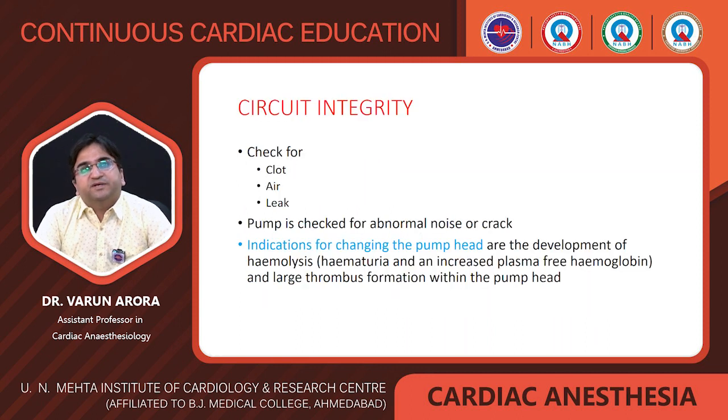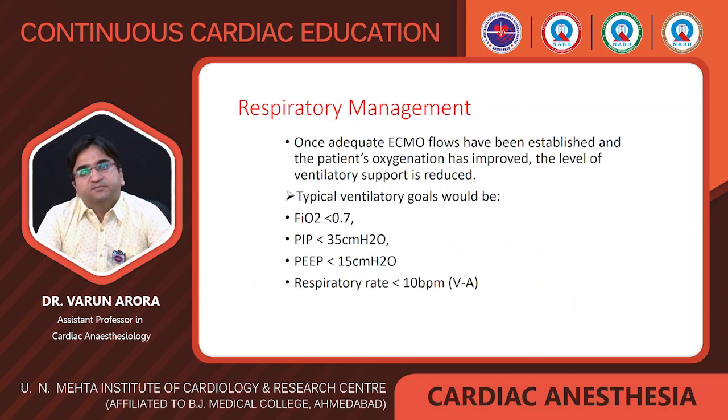Now coming to the circuit integrity. Check for clot, air and leak. Pump is checked for abnormal noise or crack. Indications for changing the pump head are development of hemolysis, hematuria and increased plasma-free hemoglobin, and large thrombus formation within the pump head. Now coming to the respiratory management.